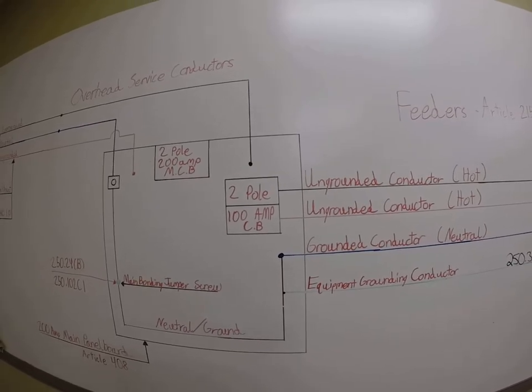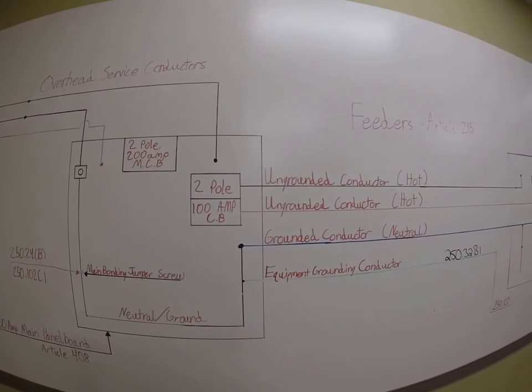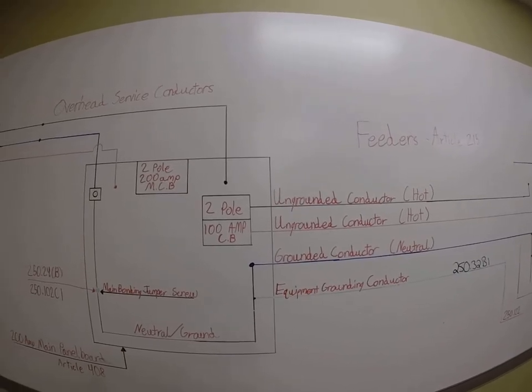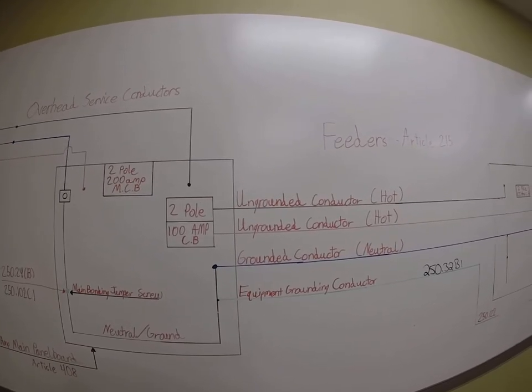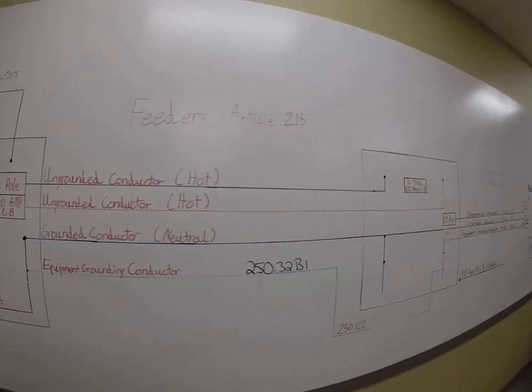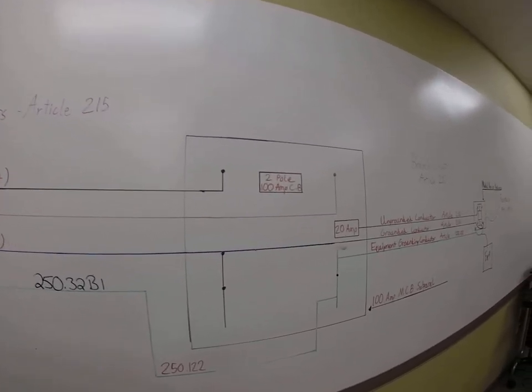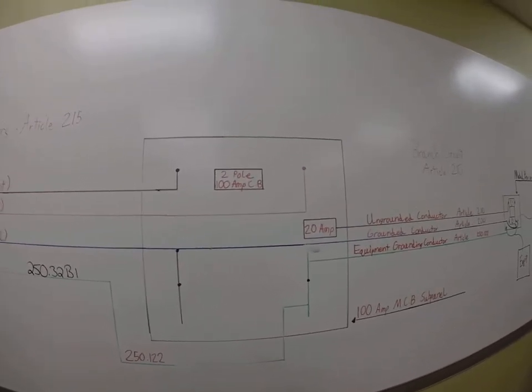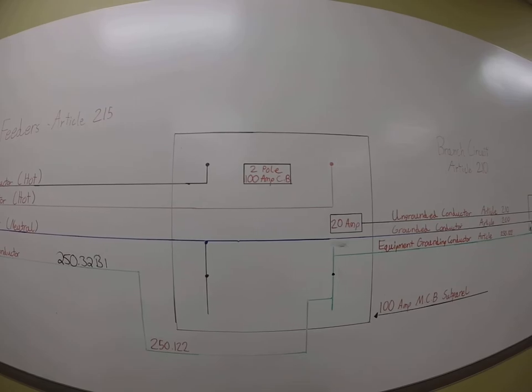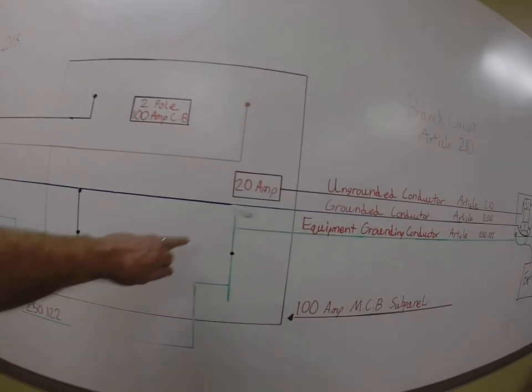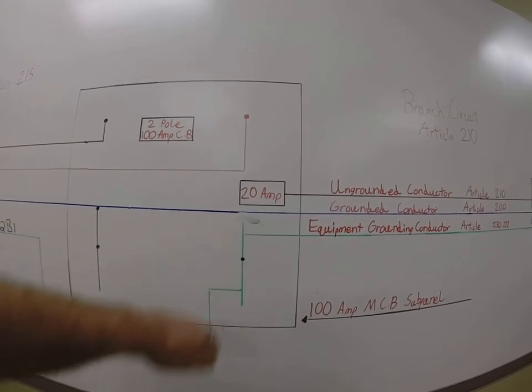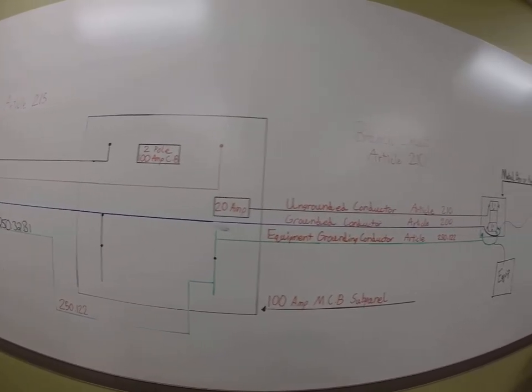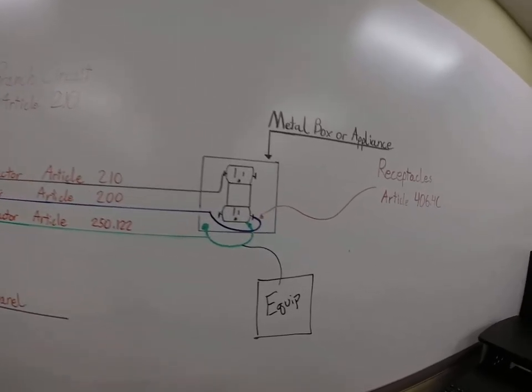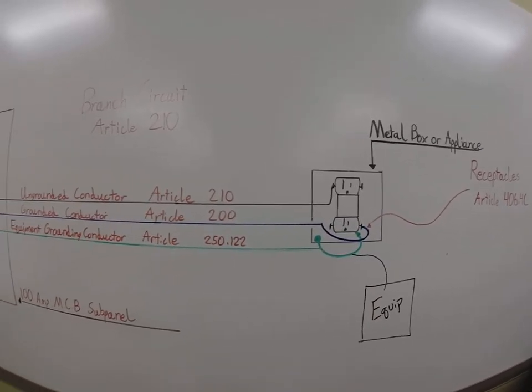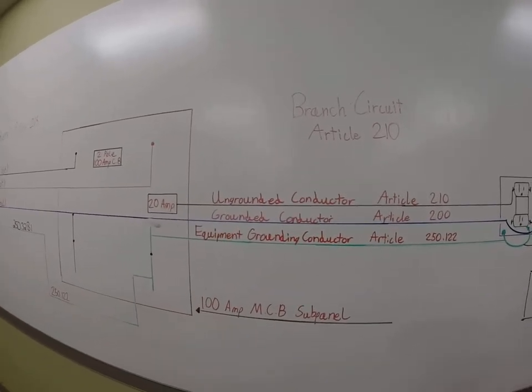You're going to get a real good theoretical explanation that if you wire a multi-wire circuit wrong, you'll create a voltage drop. That'll come in a different video, and you could be blowing up TVs and compressors and whatnot because you'll have an over voltage on one circuit and under voltage on another. Here's my sub panel. It's just showing a representation of 2 hot conductors and a neutral tied in. And once again, we don't want the equipment grounding conductor and the grounded circuit conductor bonded. We want to isolate them. And I just drew what could happen if I had a faulty piece of equipment and how those electrons want to travel on an unimpeded, isolated path back to the source.